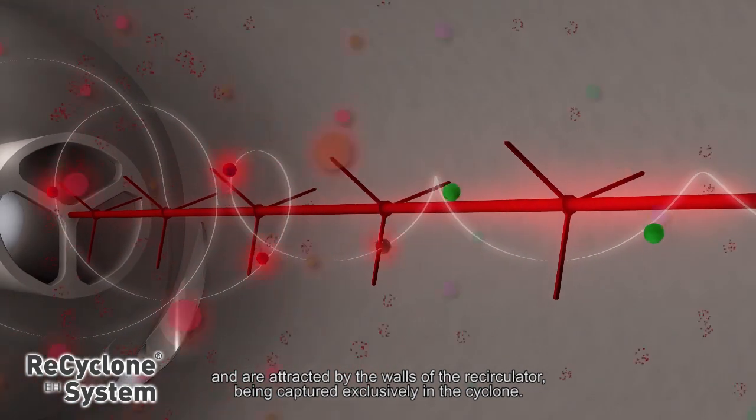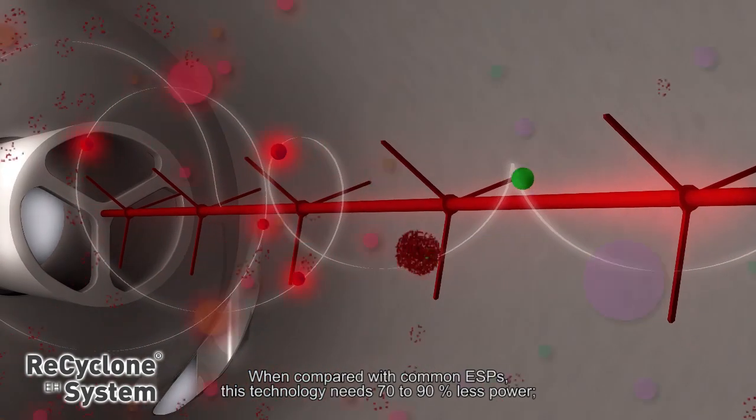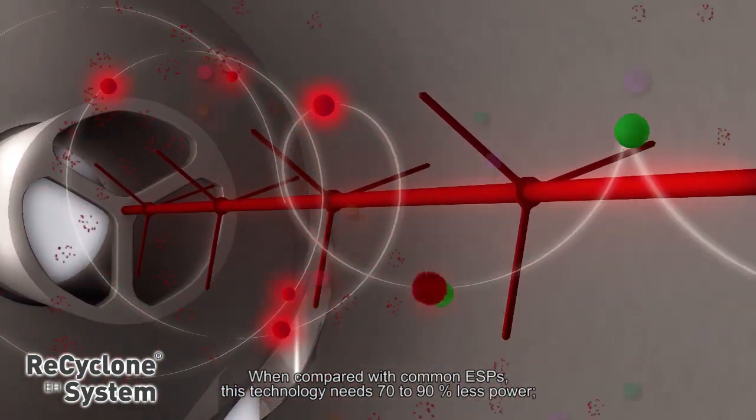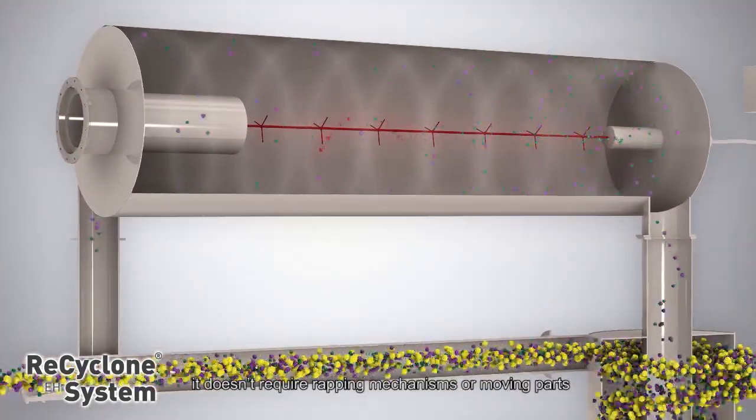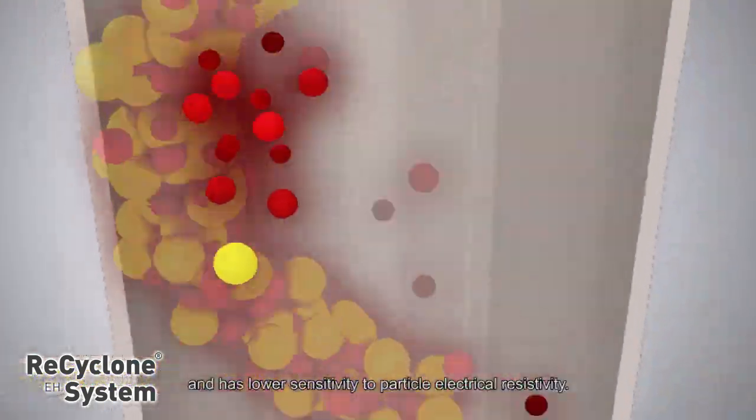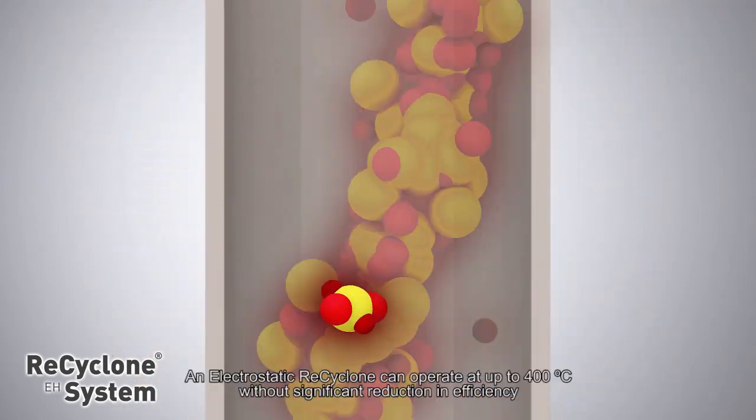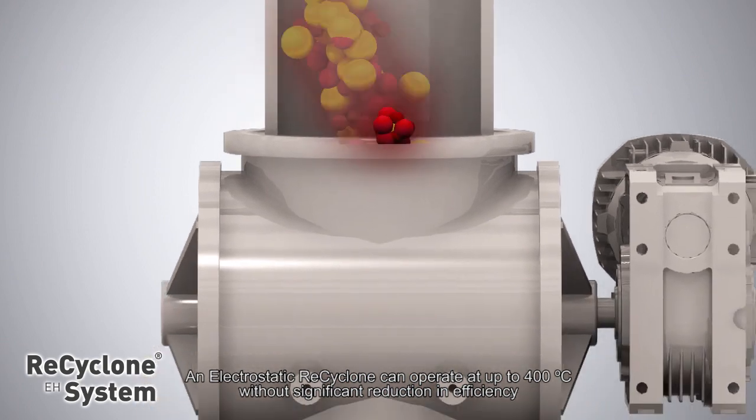When compared with common ESPs, this technology needs 70 to 90% less power. It doesn't require rapping mechanisms or moving parts and has lower sensitivity to particle electrical resistivity. An electrostatic recyclone can operate at up to 400 degrees Celsius without significant reduction in efficiency.